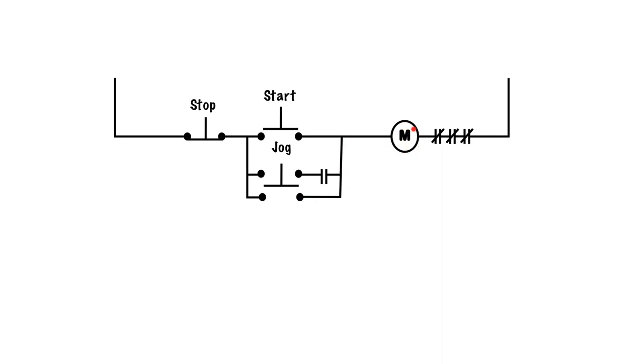But there's a problem called contact racing, in the sense that this button here, as it goes back up, can sometimes beat it back up before the coil de-energizes or these contacts open. So for whatever reason, this button, this push button bounces back quicker than these contacts can open.